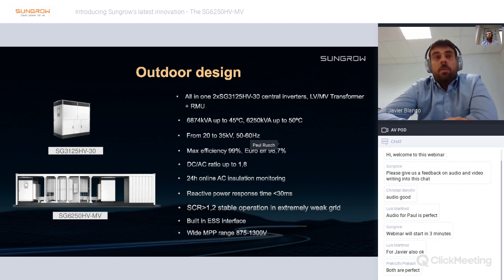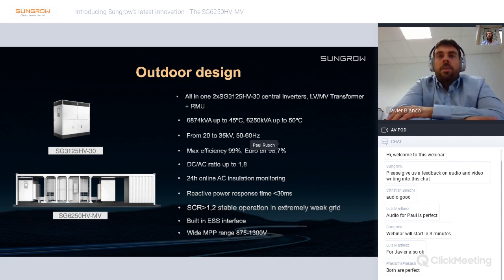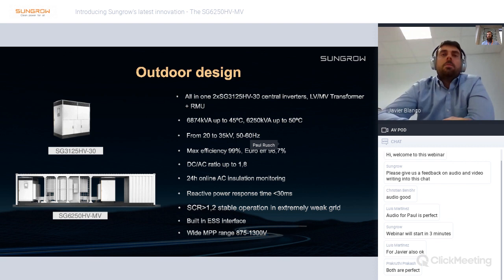Speaking about the grid support we introduced at the beginning, we have a reactive power response time below 30 milliseconds, and we can operate stably within short circuit ratios above 1.2, meaning it can work in very weak grids in countries such as Australia or India, for example, where grids can be really weak, and the operation has to remain stable even under those conditions.